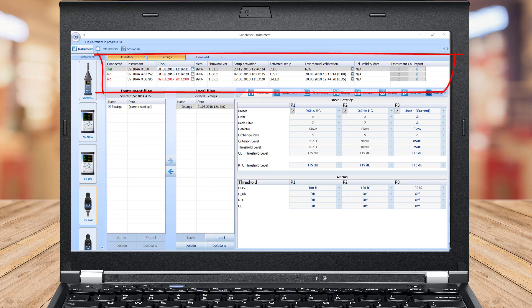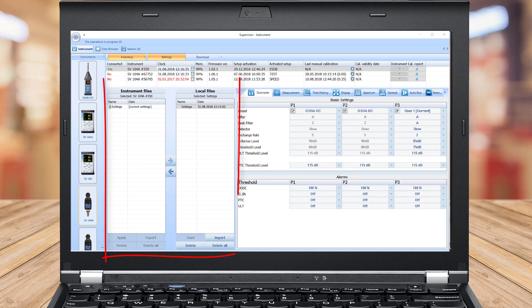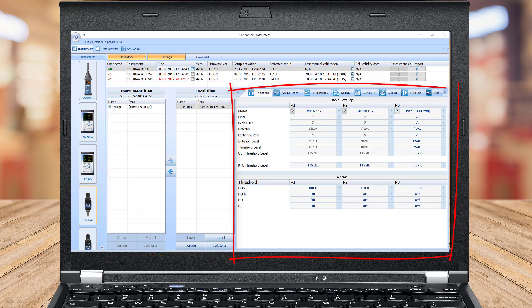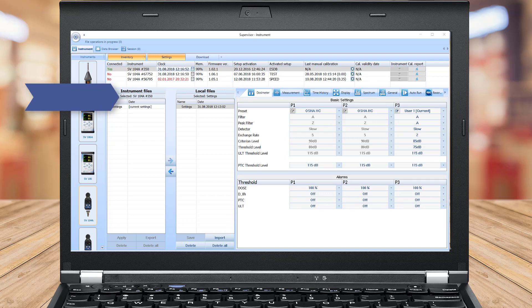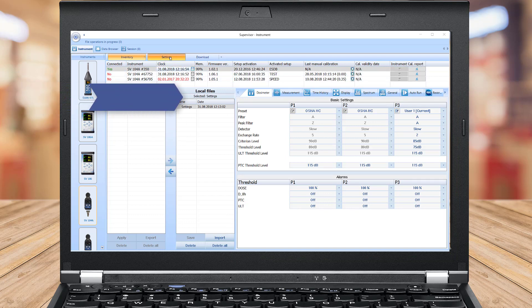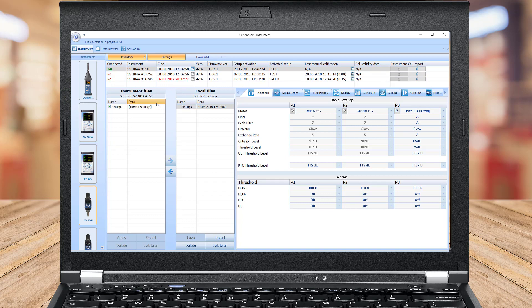The Inventory Panel detects all SV-104A connected devices. The Quick Access File Manager enables you to copy configuration setup files between the computer and instrument internal memory. The Instrument Configuration Panel enables access to all measurement-run configuration settings. The idea behind the configuration setup is to download the configuration setup file from the instrument to the computer you are working on and refer to local files as the destination.